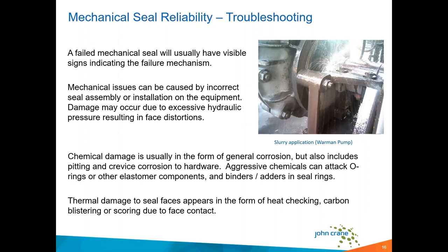We could develop excessive hydraulic pressure that's going to result in face distortion, secondary seal extrusion, and erosion due to high velocity in certain areas around the seal. That's something that we look at in the analysis, particularly if you have abrasive particles present in the fluid itself. Face contact wear, if it's more severe, is really going to tell us that there's insufficient hydrodynamic fluid film support. That's a fancy way of saying not a lot of lubrication, or inadequate lubrication, at the seal faces.